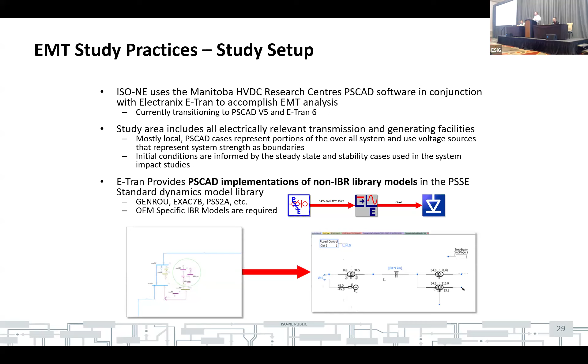The ETRAN software also lets us take dynamic models that we wouldn't normally ask for, say from an OEM or a developer, and port them right into their equivalent model in EMT space. That's what this diagram is showing -- we start with our PSS case and convert it into a PSCAD case. Normally the system is much larger when doing system impact studies, with hundreds of buses, but that'd be hard to put on a slide here.